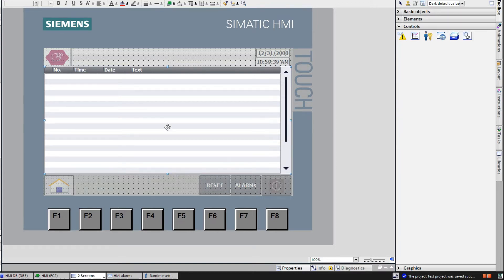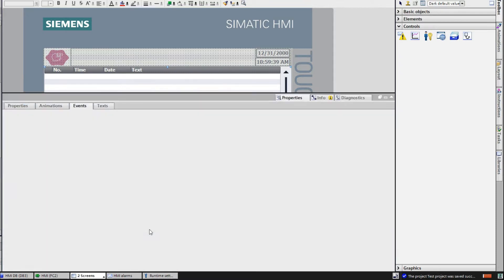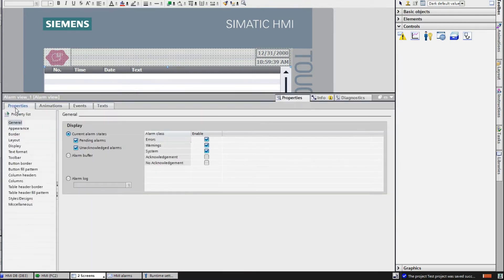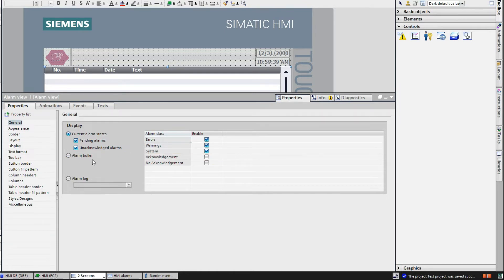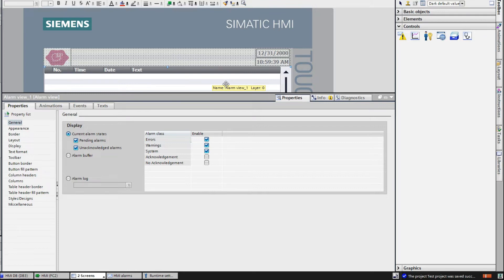On the right side you can see the scrollbar. If you go to properties of that alarm viewer by right-clicking, in the General tab you can see that this alarm viewer will display the current alarm — meaning the pending alarm which is not acknowledged or reset. If you choose 'alarm buffer', then this alarm viewer will show the current alarm plus the earlier historical alarm.